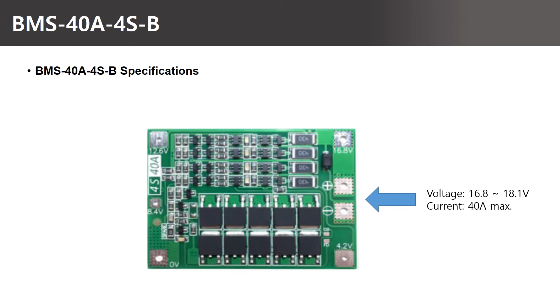Let's take a look at the specifications. The charge voltage should be in the range of 16.8 to 18.1 volts. The current for charging and discharging should be limited to 40 amperes for continuous operation. Overcurrent protection is activated in the range of 70 to 90 amperes.